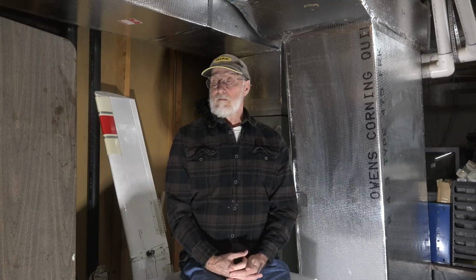And of course, the blower wheel is always there. Cleaning a blower wheel that has quite a bit of dirt in it sometimes makes a pretty spectacular difference in how well that thing performs. When you're working with ductwork, you do need to consider those internal components when you're trying to figure out what's wrong. If you have a freezing up air conditioning coil and pressure drop across it isn't too bad, but you don't have a lot of static pressure to start with, then you've got to look inside this thing. Pull the blower off, look at the secondary heat exchanger, and of course, look at the blower wheel.